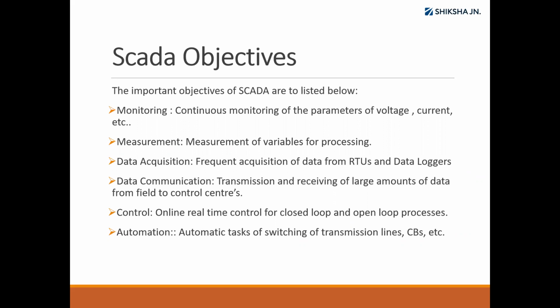Then data communication: transmission and receiving of large amounts of data from the field to the control center, every day, every moment, every millisecond. If you're working in a thermal power plant, you might have thousands of field instruments—many flow transmitters, pressure transmitters, temperature transmitters—accessing and sending data every millisecond. So where will you put all this? This large amount of data has to be logged somewhere: some in Excel sheets, some in SQL servers, or third-party software through which you want to access and store the data. For all this purpose, you require a SCADA system.